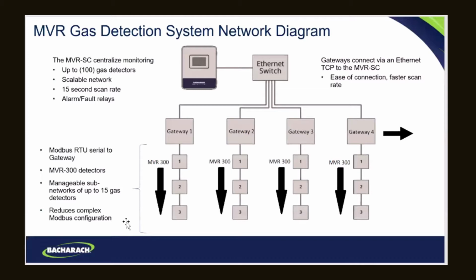No, with Ethernet, there should be almost no limitations. Now, when you start to talk about Modbus, though, there may be some Modbus limitations, and that typically has to do with whether you have a simple Modbus network where each one of these legs is under 1,000 feet, which I think is reasonable with only 15 gas detectors. Because if any Modbus network gets to be over 1,000 feet, then you have to start considering signal conditioning and repeaters and all that other kind of stuff to make sure that the signals don't degrade. If you keep it 1,000 feet or less, you don't have to worry about it. I don't think we'll be anywhere close to that just because the patient rooms are all jammed together. Yeah, right. That's what we find.